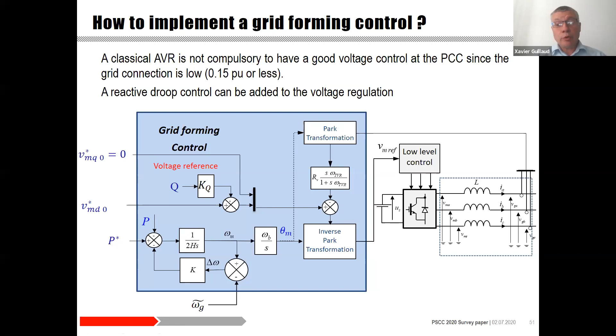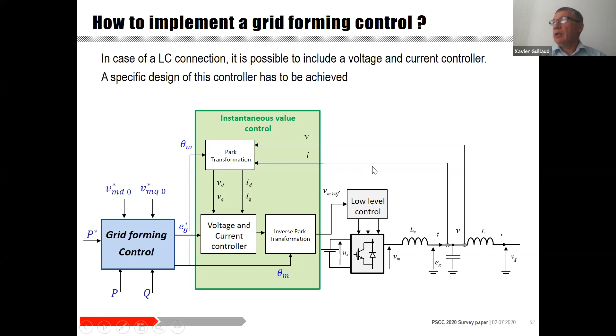In case of a two-level VSC, an LC filter is added between the VSC and the point of common coupling. Current and voltage loops have to be implemented. With this kind of system, the grid forming control generates the voltage angle reference for the voltage across the capacitor and not the modulated voltage anymore. A specific design of this control has to be achieved for that.